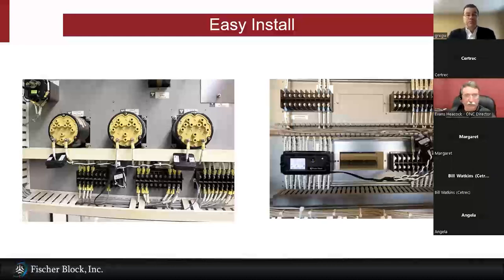So this can tie to a flexi test on the back side or the front side of the panel? That's right. When we connect to the front side, it actually acts as a retrofit cover, replacing the existing cover on a flexi test switch with just 2 thumb screws - same attachment and removal as a normal test switch cover on the front. On the back, we just have a special bracket that takes advantage of the existing bolts on either side of the test switch. So it's a situation where you don't need any additional real estate on the panel, and it's just a 5-minute install in that case.